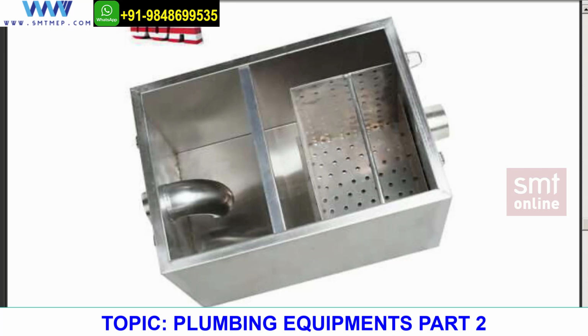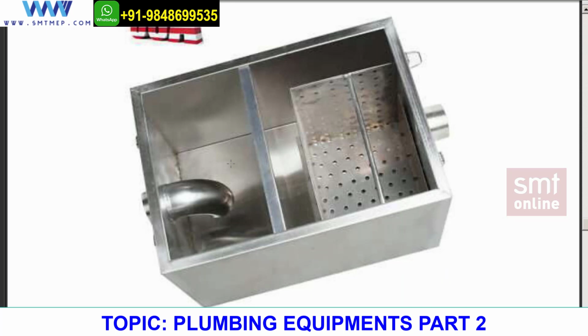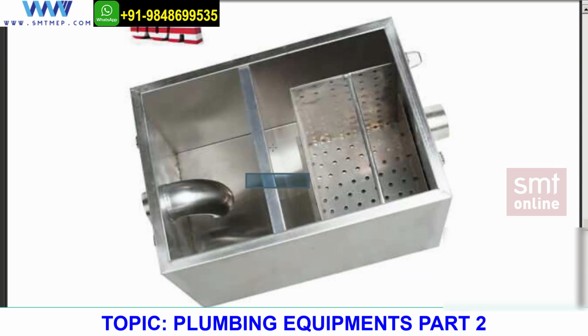That's why I do have a strainer over here. Okay. Next is what happens when it has been draining out in this manner. So now, as this is cooling down, first of all, this water has gone here. Again, it is coming here. In the meanwhile, the water which was warm or hot will be getting cooled. The moment it gets cooled, the oil and the grease will be separated automatically because the temperature is not the same. And we know this, oil floats on the water. So it goes at the top.